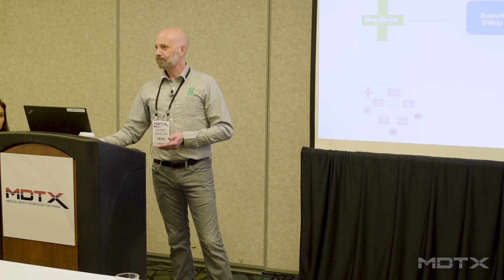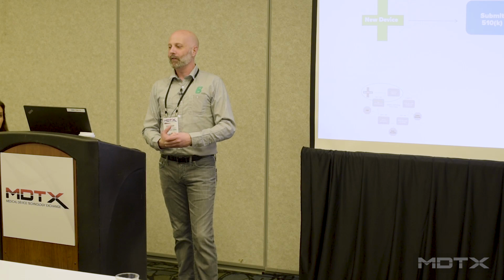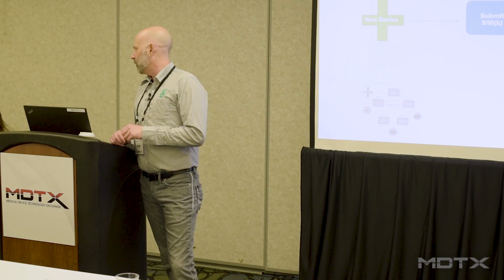All right, so new device, submit your 510K. There's a format, as I talked about a moment ago. There's a user fee, and the user fee actually went up. It almost doubled this past year for 510Ks for the standard fee. To submit a 510K, you got to pay money. You got to pay about $10,000 unless you're a small business. Small business has not changed that much. It's like $2,600. And small business, in the terms of FDA, I think it's sub 100 million. It's a pretty big threshold for being a small business. So most of your companies probably qualify for being a small business.